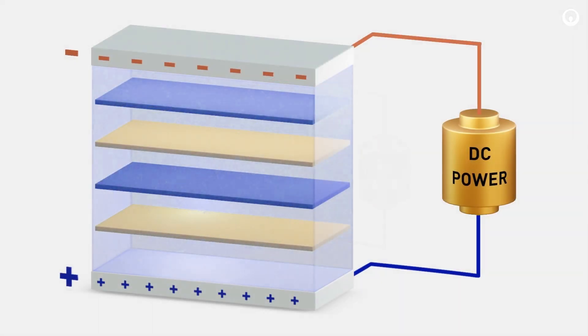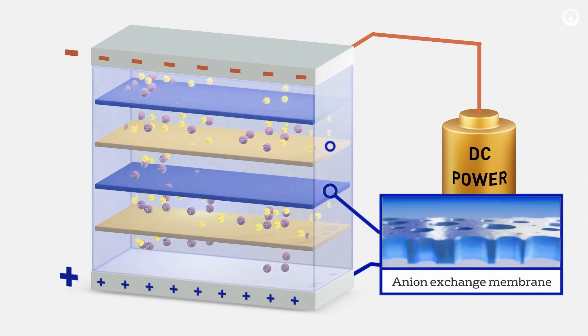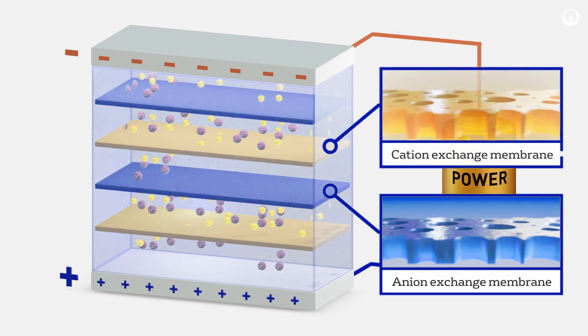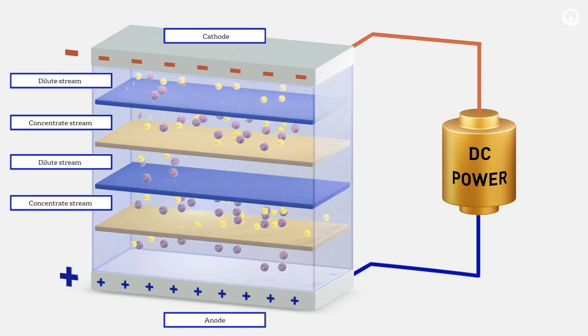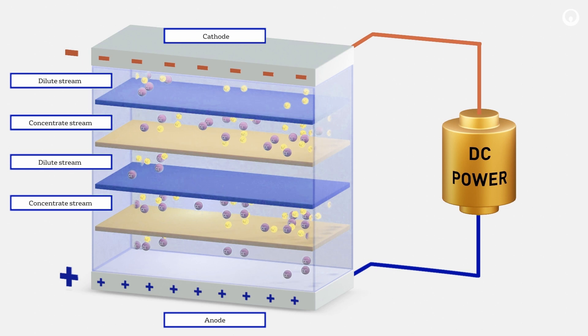Electrodialysis is an advanced membrane technology that utilizes this ion movement to desalinate water. The ions move through selective ion exchange membranes, which only allow either cations or anions to pass through them. By alternating these membranes with spacers between them, it creates two separate streams: a desalinated stream and a concentrated salt stream.